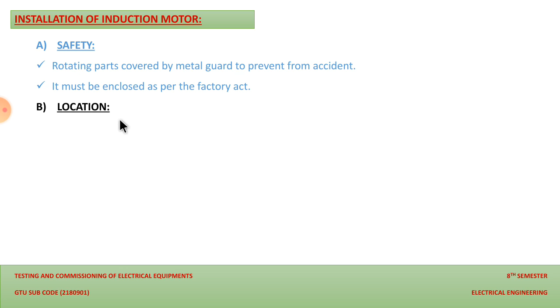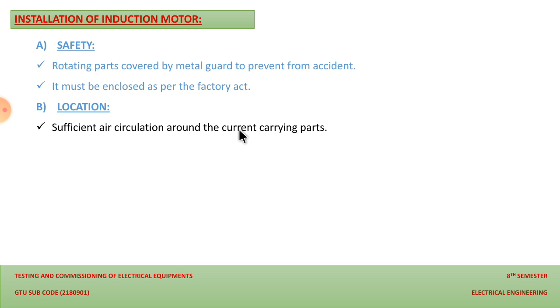The second point that we should keep in mind while we are installing our induction motor is location. Sufficient air circulation is needed around the current carrying parts. As the motor has conducting parts inside, when we increase the load, the circulation of current will increase and the winding will get heated up. If proper ventilation is not provided, that can permanently harm our machine. So sufficient air circulation is necessary surrounding the current carrying parts.